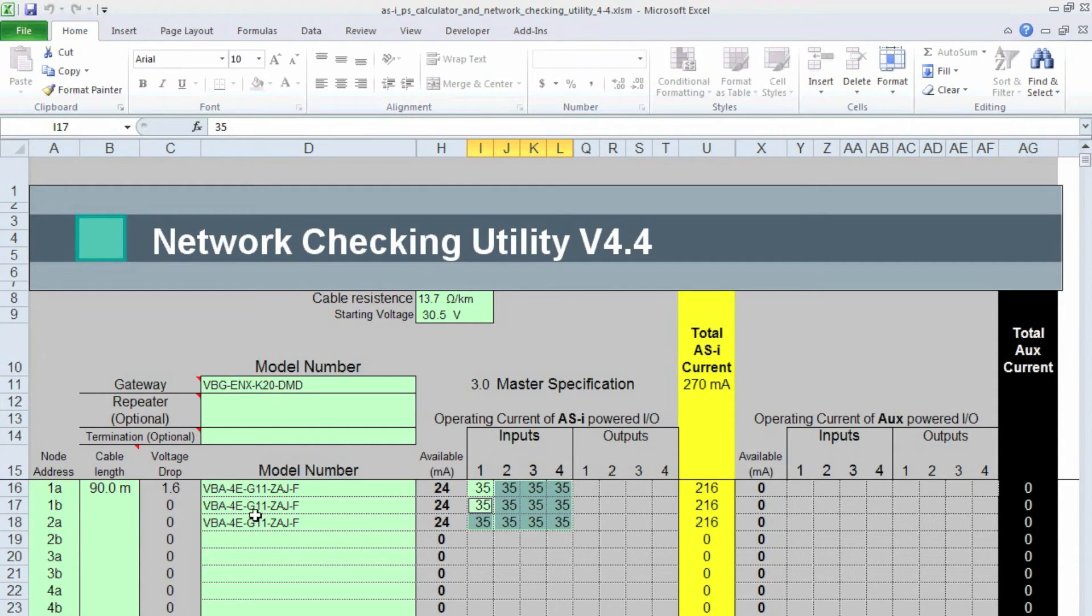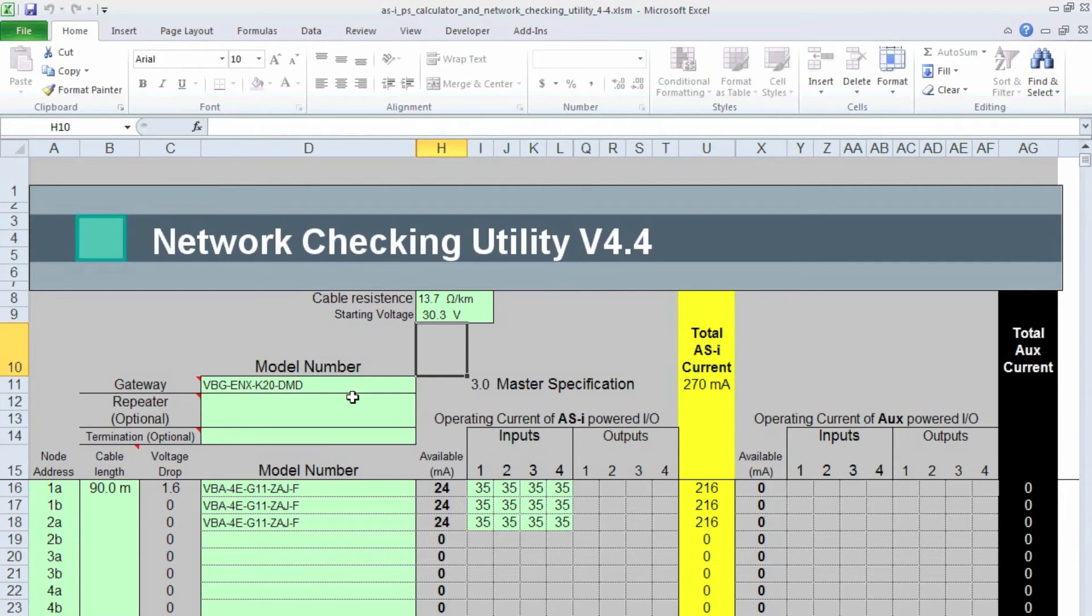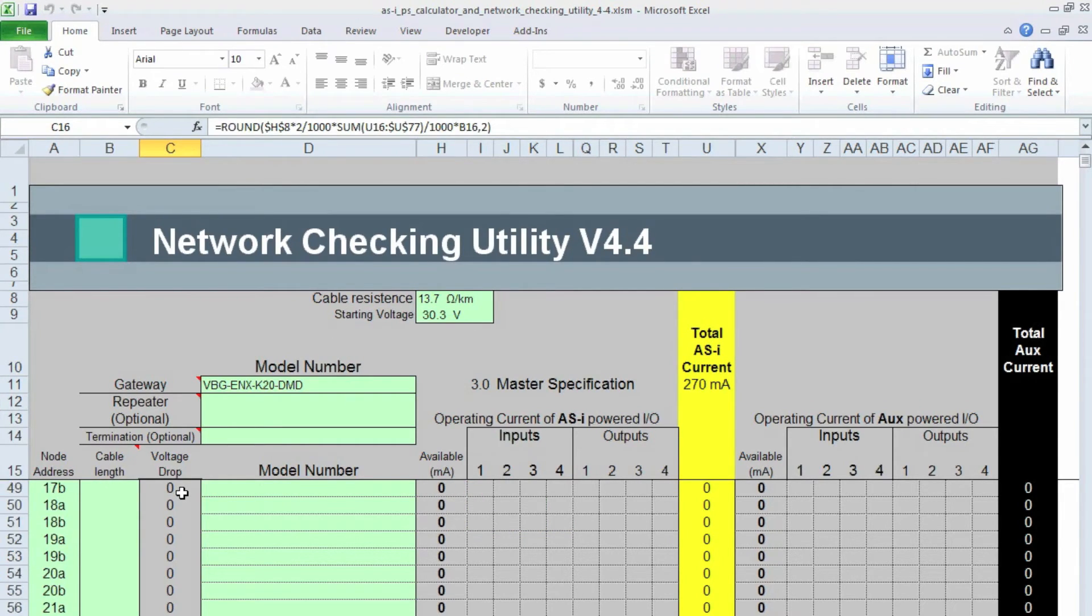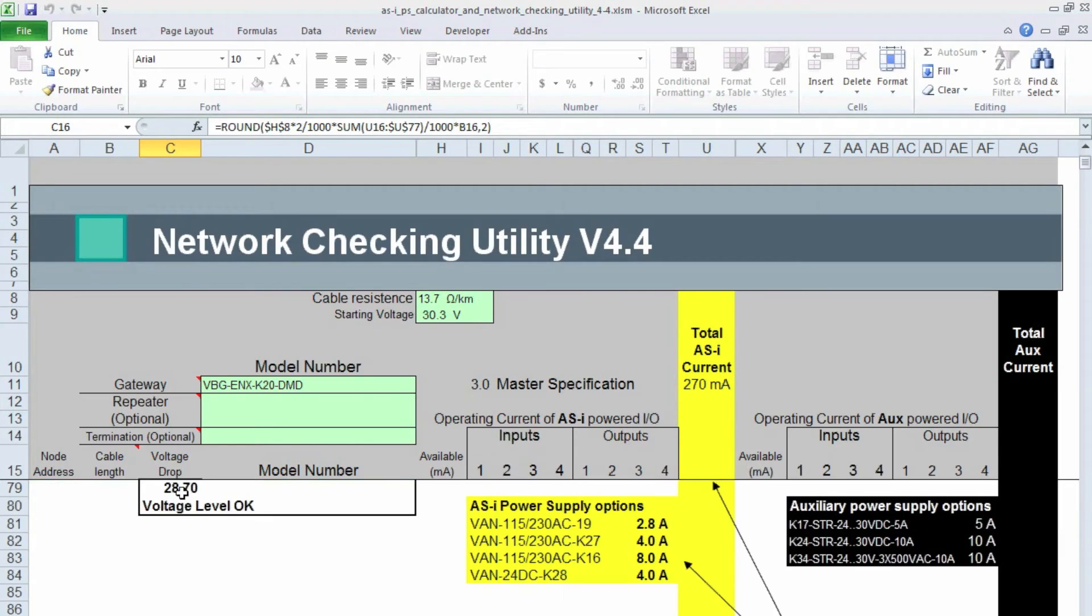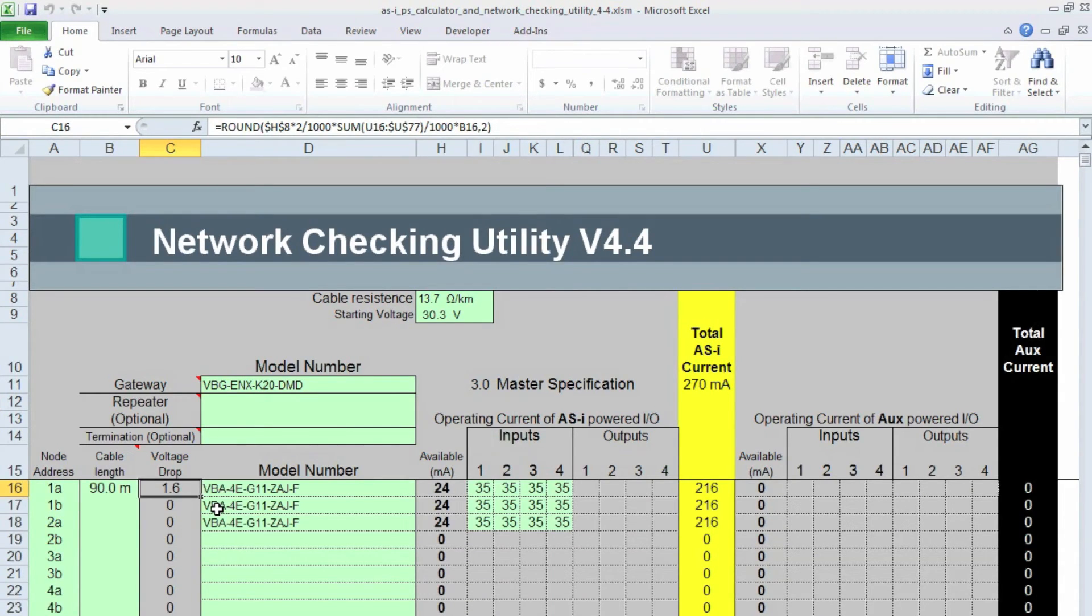And I'm just going to copy this and paste it to the rest because I had all the same sensors. All right, so now I pasted that in. Now you can see there's only a 1.6 volt drop starting at, actually it was 30.3, the power supply that I use. So I'm going to put that starting voltage here. And the total voltage at the end was 28.7. And that's great because it's above the 26.5 volts that I want. That the operating voltage of all of my modules is.